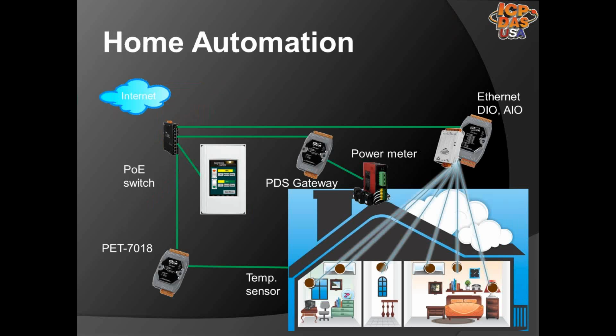Power meters are being used for home automation. Information is gathered from sensors attached to data acquisition equipment. Lights can be turned on based on light levels or room occupancy. Energy can be monitored and the information can be displayed on a touchscreen controller. The energy usage data can show as green or red if the energy usage level is in a desired range or not. The information can be brought for viewing on a web page through programmable device servers or serial to Ethernet gateways for RS485 Modbus RTU-based devices.